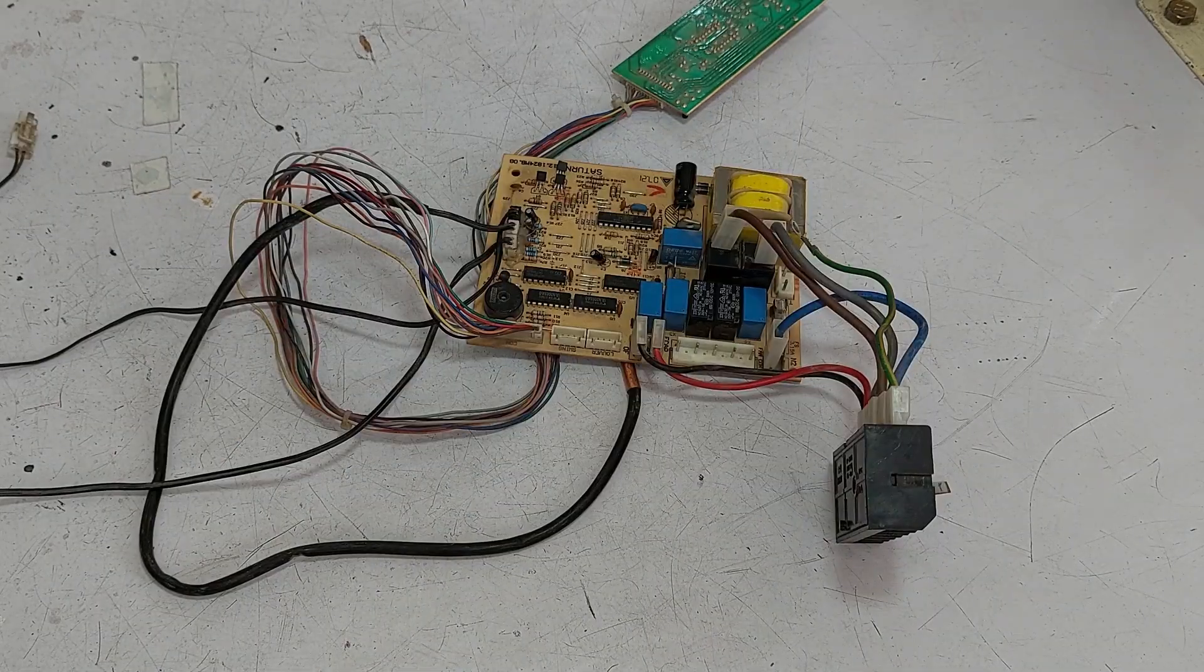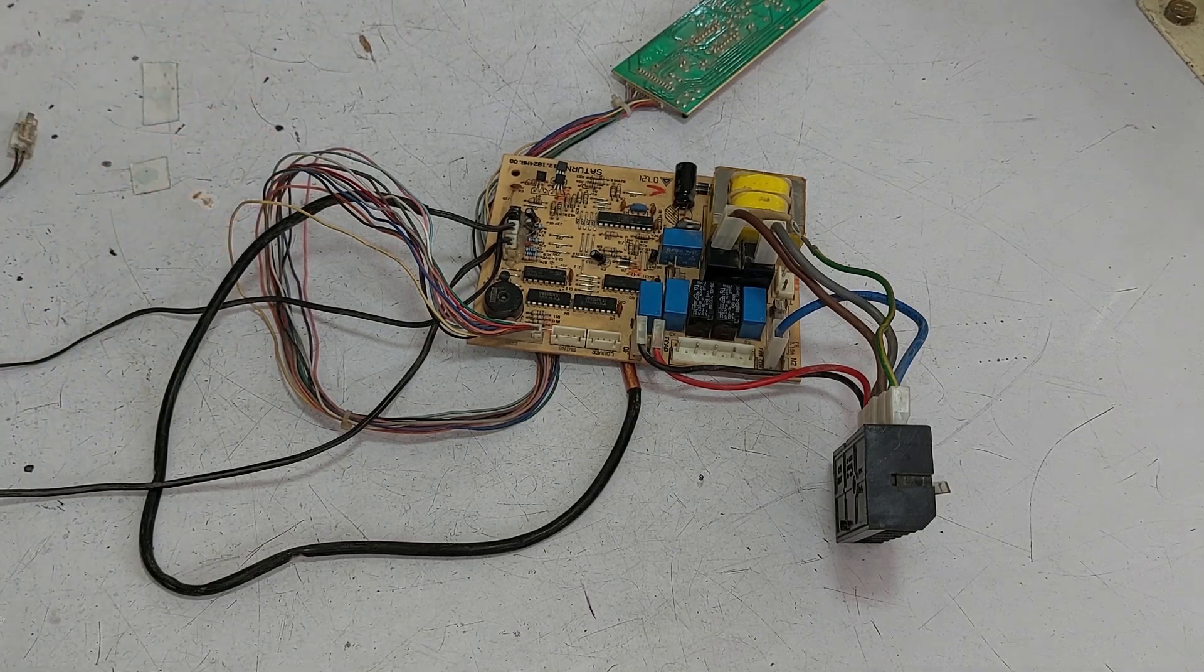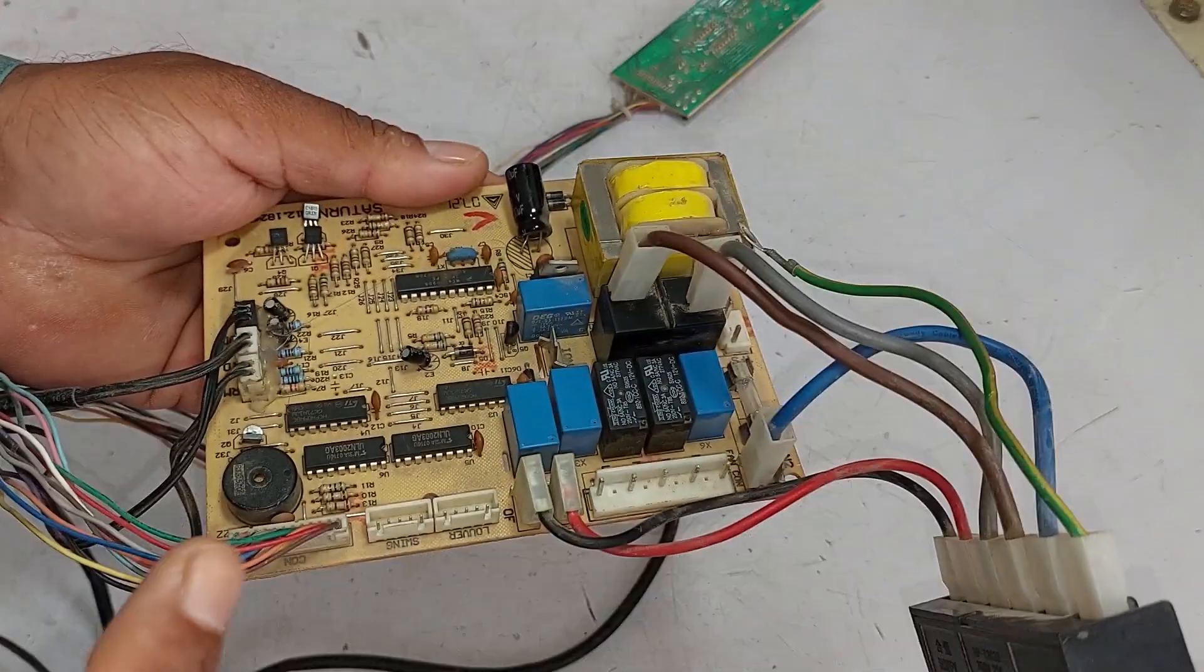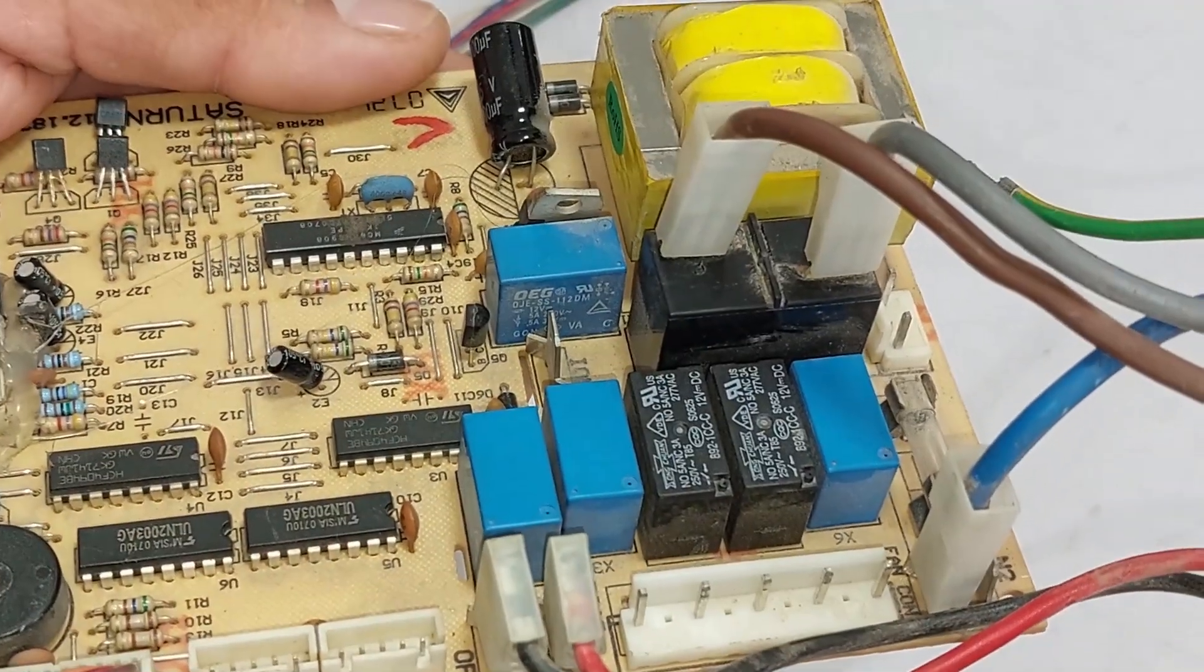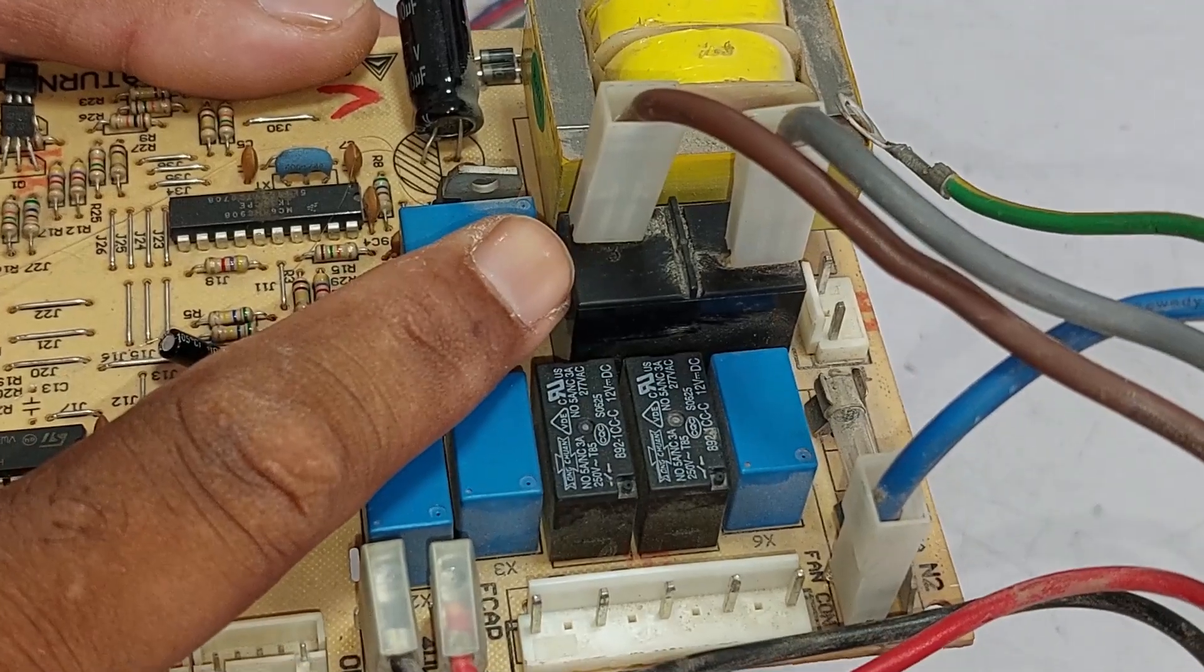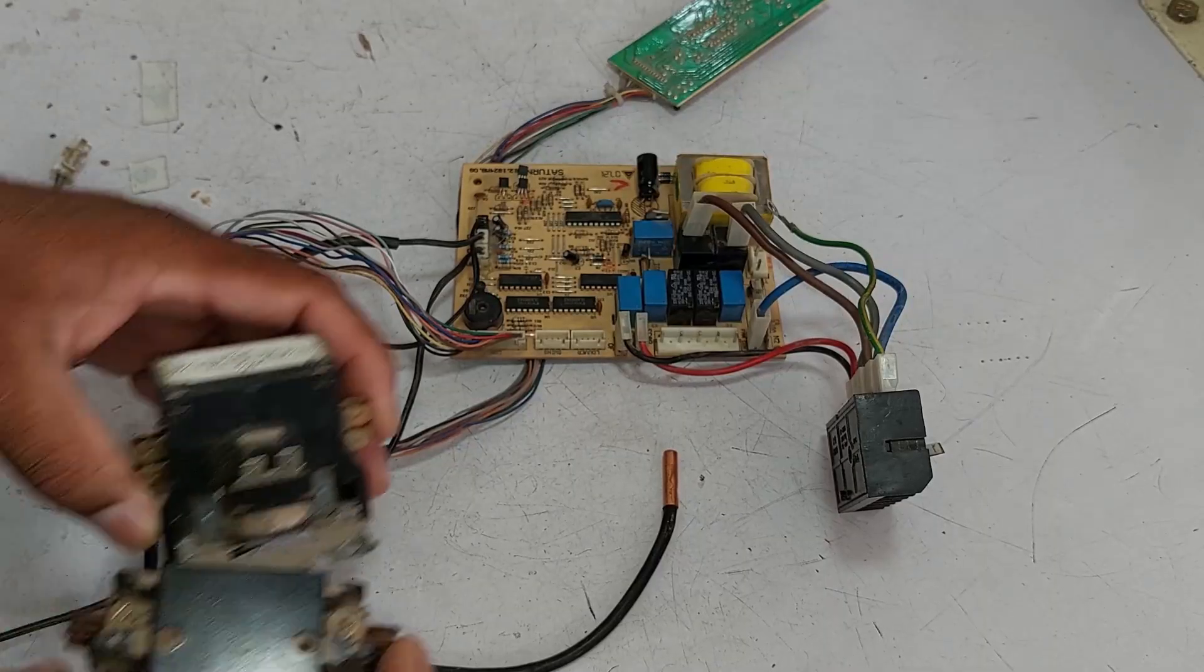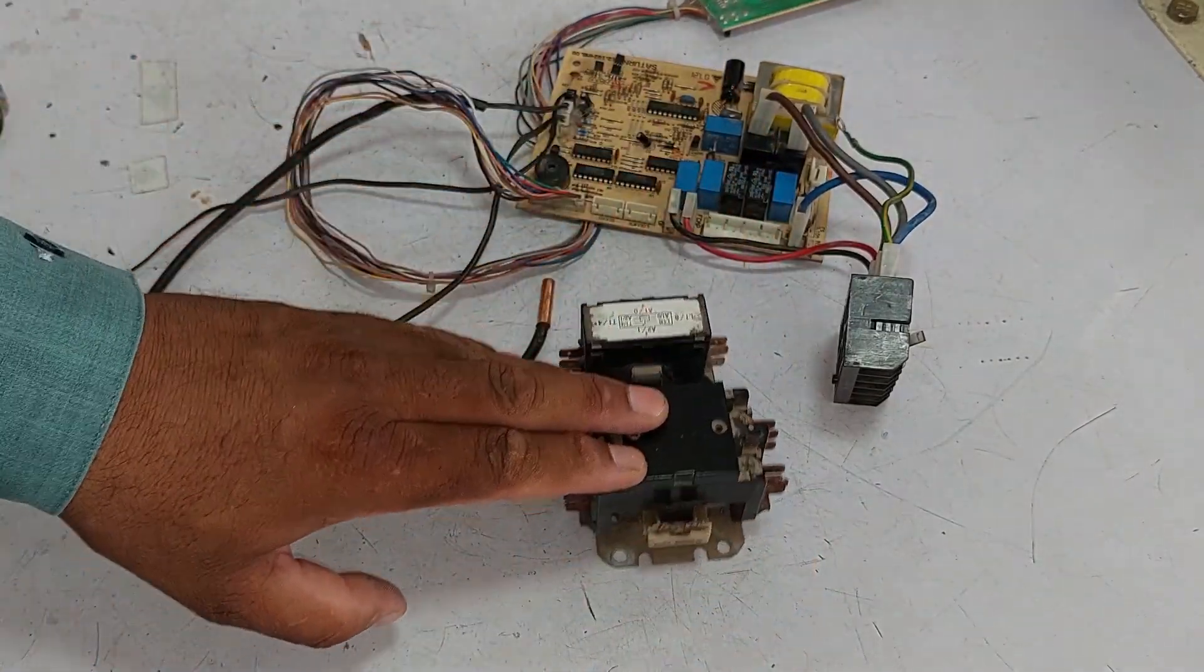Now let me explain the system used in 2 ton and 2.5 ton units. These units operate similarly, but there are some key differences in the components. In 1 ton and 1.5 ton units, the relay directly handles the load of the compressor. However, in 2 ton and 2.5 ton units, smaller relays are used, but the same function and procedure apply. The difference is that these units use a contactor to manage the compressor's load.